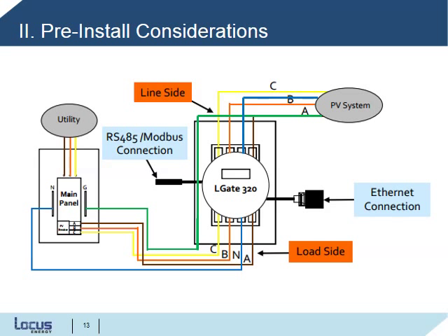Here, an overview of the LGate 320 installation. This meter will also be mounted in a meter socket between the PV system and the main panel, with the AC lines run through the meter socket line to load. Now that we've covered the general line diagram, let's talk about a few things to keep in mind to ensure a successful installation.